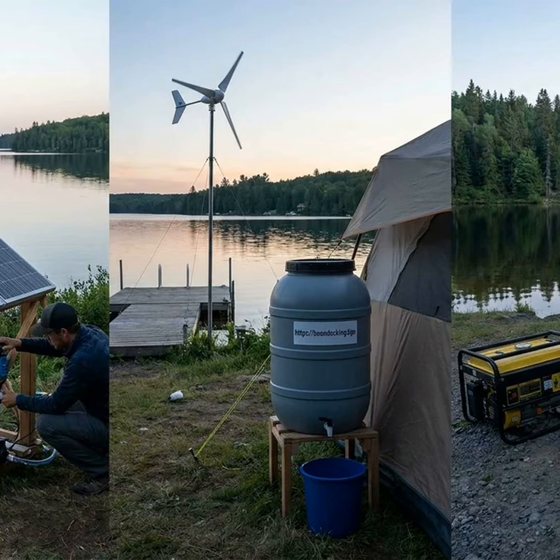In sum, the power system might be 1.5 kW PV, plus 0.4 kW wind, plus 0.5 kW microhydro, feeding into a 48V 30 kWh battery bank with a 3 kW generator backup. This setup can produce 15 to 20 kWh on a good summer day, enough for critical loads, lights, pump, small fridge, and perhaps only 2 to 5 kWh per day in deep winter.